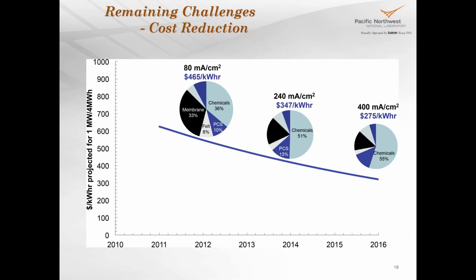So what's next? You can see this pie chart that talks about the cost distribution as we increase the current density from 80 all the way to 400 milliampere per square centimeter, and it's very evident that the vanadium chemical becomes a dominant cost at 55% at 400 milliampere per centimeter square.